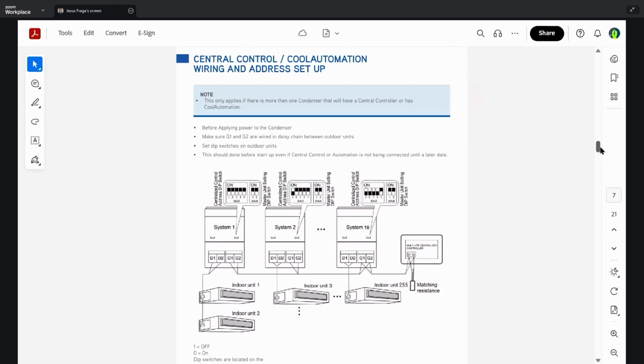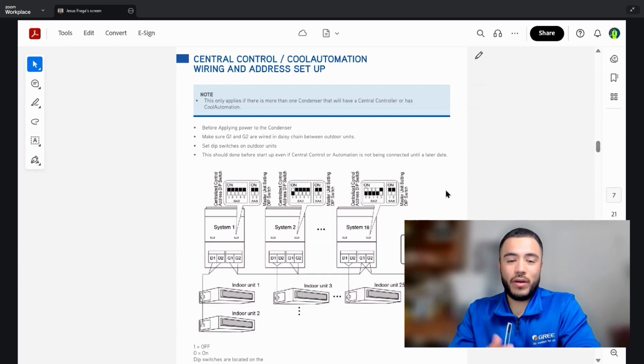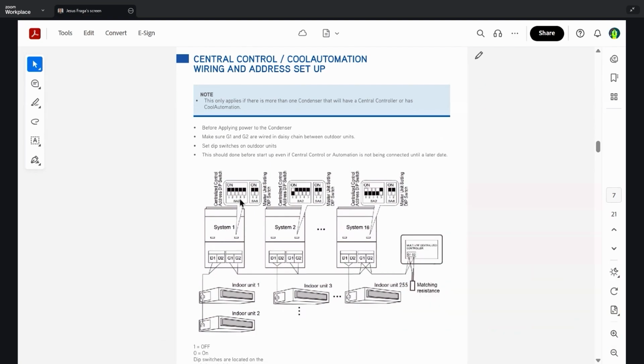So moving on to central control and CoolAutomation wiring and address setup. As I stated earlier on the previous slides, a lot of this information stays the same, so the same applies here. The note here is this only applies if there's more than one condenser that will have a central controller or CoolAutomation. So if we have, for instance, 16 systems in line here, the addressing strategy is pretty simple. As we see here, this is always going to be the first system, because all the dip switches are in the off position. Once we go to the next system, we flip the first, then we flip the second, and so on and so forth. We'll see that in the chart on the next page for you guys.